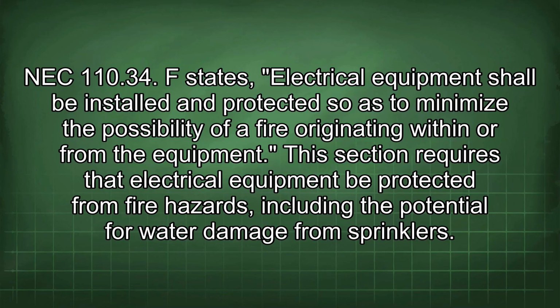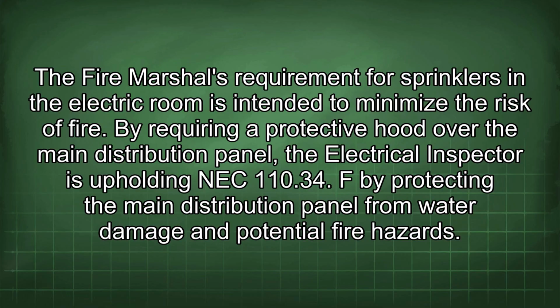110.34.F states, electrical equipment shall be installed and protected so as to minimize the possibility of a fire originating within or from the equipment. This section requires that electrical equipment be protected from fire hazards, including the potential for water damage from sprinklers. The fire marshal's requirement for sprinklers in the electric room is intended to minimize the risk of fire. By requiring a protective hood over the main distribution panel, the electrical inspector is upholding NEC 110.34.F by protecting the main distribution panel from water damage and potential fire hazards.